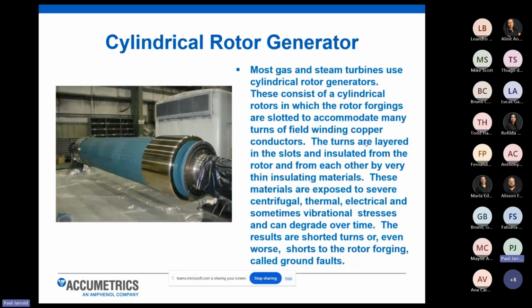So again, most gas turbine generators use a cylindrical style rotor like the pictures I'm showing here. It consists of that cylindrical rotor and the forgings that are slotted inside that rotor to help install the copper bus bars or copper conductor field windings. And the turns are all layered in that slot, insulated from themselves and primarily insulated from the rotor.